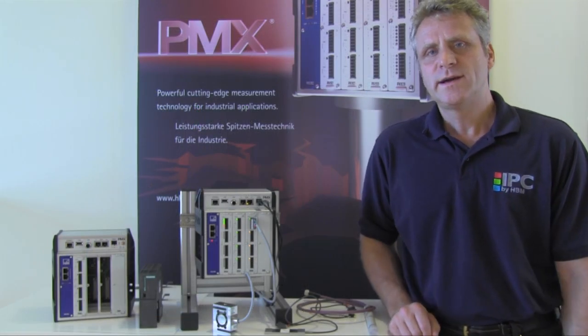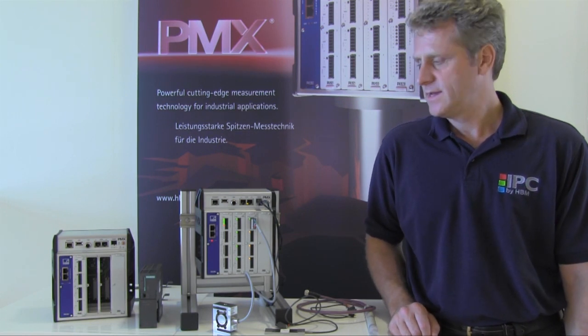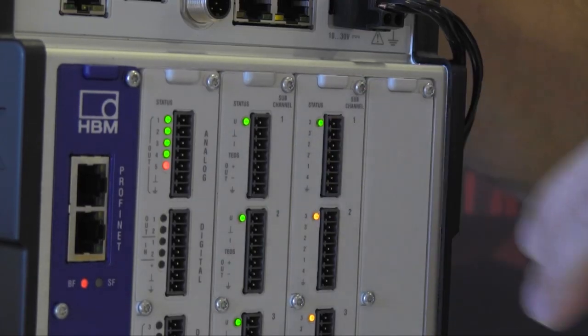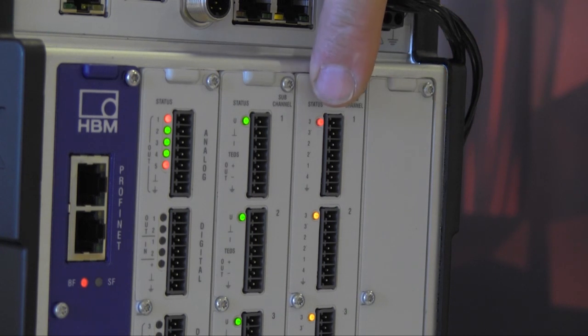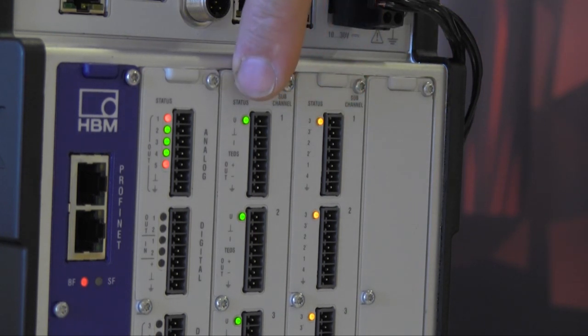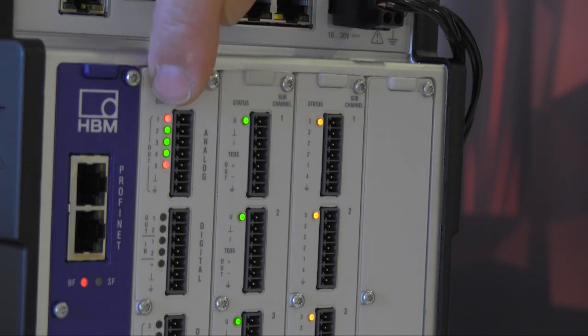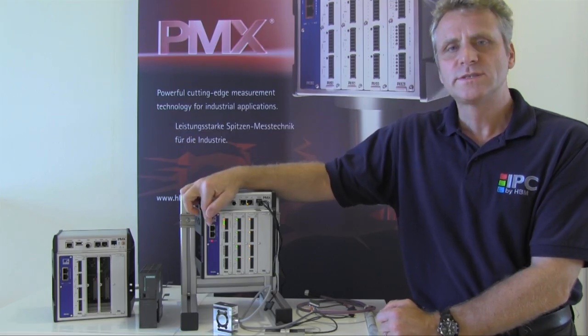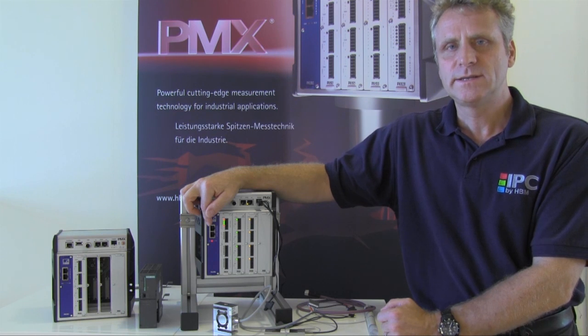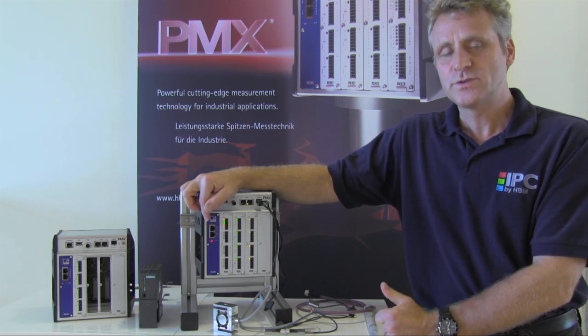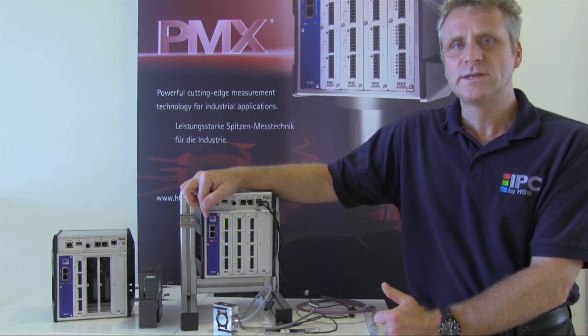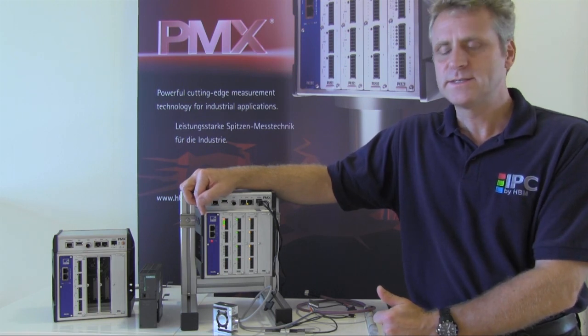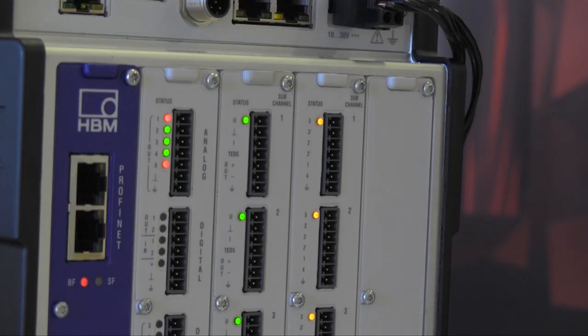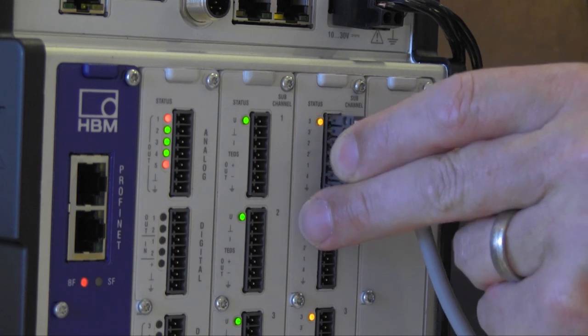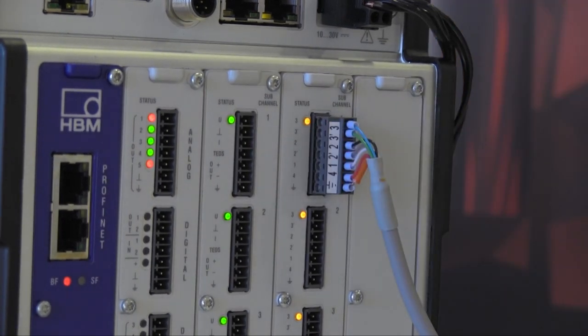Malfunctions can be detected easily in later operation of the application by the system LEDs. A broken wire or disconnected sensor is indicated by a red LED. This status can also be forwarded to a controller via the digital outputs or the field bus. This ensures fast service and repair and short downtimes. After the sensor is connected, the device detects the sensor and goes back into measuring mode.